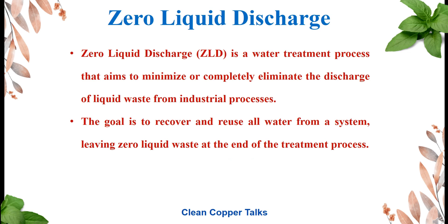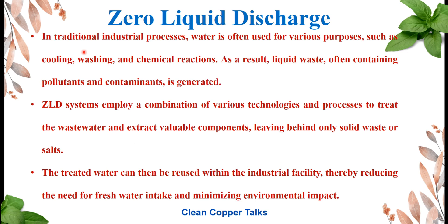In any industry, water is required for different types of operations such as cooling, washing, chemical reactions, and production. When water is used, it generates a lot of wastewater. The thumb rule is around 70 to 80 percent of water taken in comes out as wastewater — this varies largely industry to industry. The wastewater generated is highly contaminated, with BOD, COD, and other pollutants much higher than typical sewage.